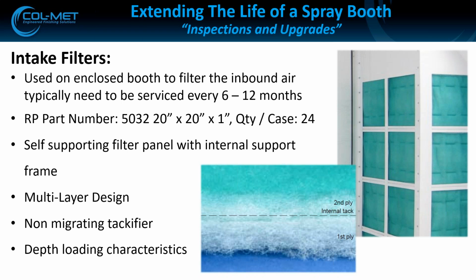So we want the more open side of the filter facing the airflow first, which in an intake filter is the white side. On exhaust filtration with split expanded paper, that's the paper side, since it's wider. That gives us the chance to catch the bigger particles on a surface built to handle it. The tacky side of an intake filter is our finest filtration layer.